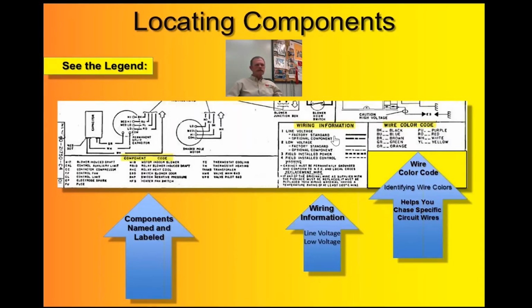Line voltage, factory standard, is usually a heavy solid black line. Low voltage, factory standard, is a light solid black line. Then you have field installed power and field installed controls, using the same concept: line voltage is a heavy dash line, low voltage is a light dash line.